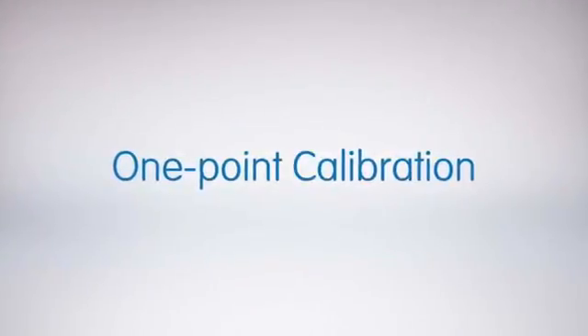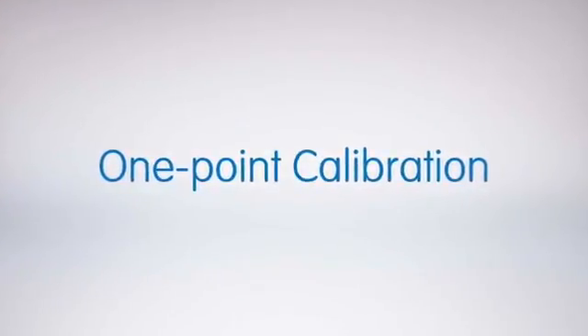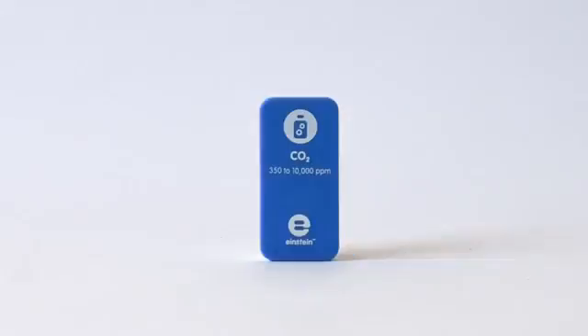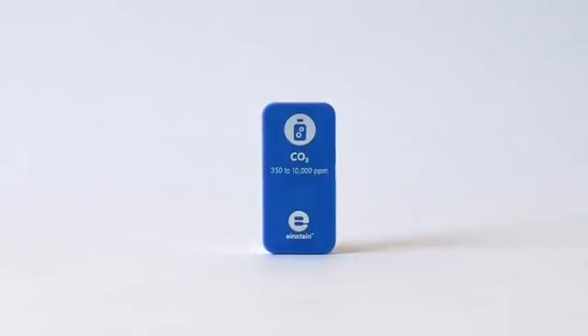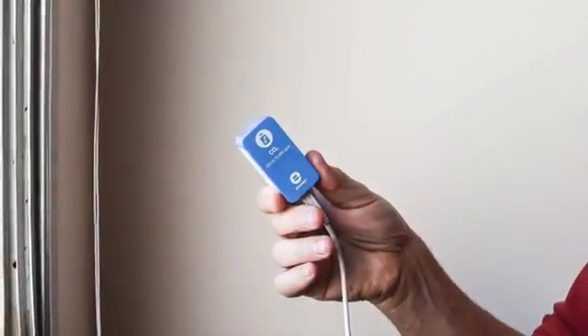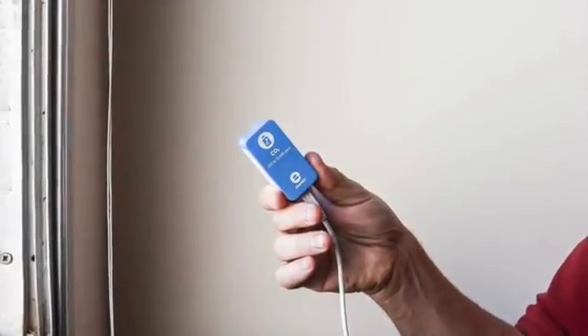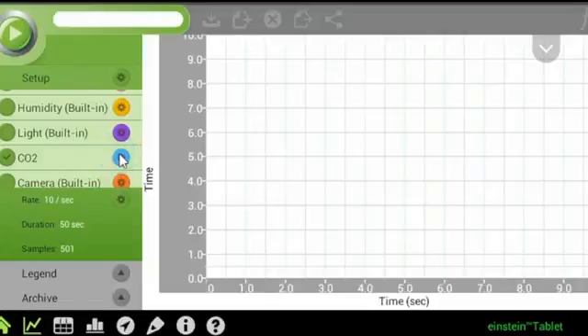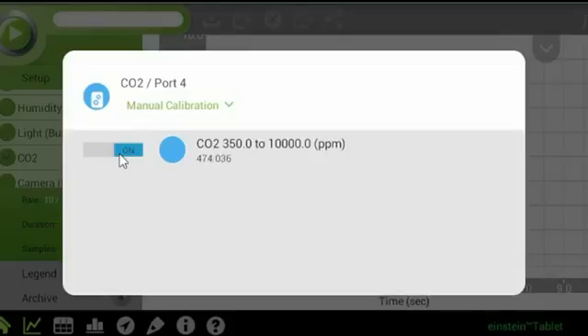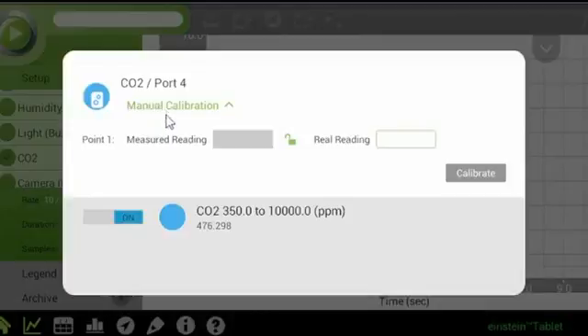1-point calibration is used with the oxygen and carbon dioxide sensors, among others. In this demonstration, we will use the carbon dioxide sensor as an example. For an accurate reading, make sure you are in a well-ventilated area. First, tap the setup button, then tap manual calibration. The sensor will start measuring the carbon dioxide level in the air.